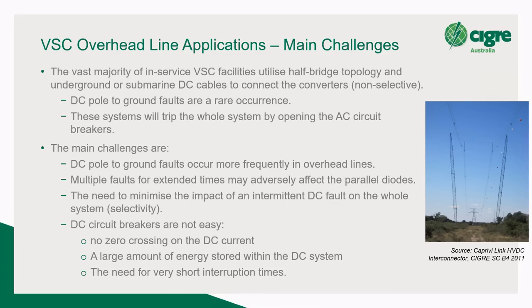It's also an issue with the parallel diodes in the VSC submodules, that they can only handle a certain number of faults or extended faults. So you want to be able to operate quite quickly in the event of a fault. If you've got an underground cable and you're only expecting maybe two or three in the lifetime, that's not such a big deal. But if you're expecting a couple of these a year, then that's something you really want to be able to control, that DC fault current.